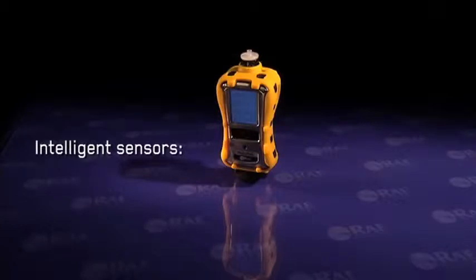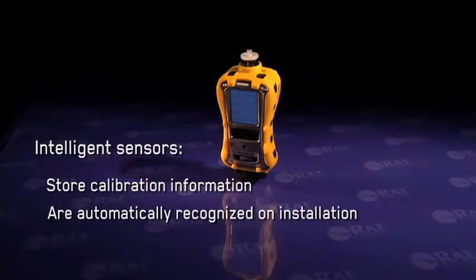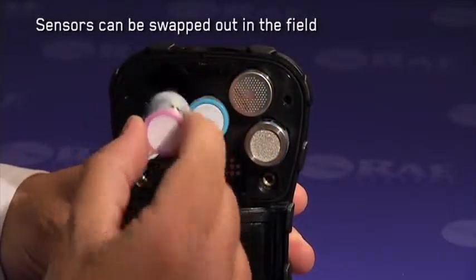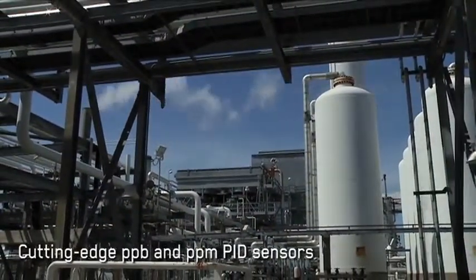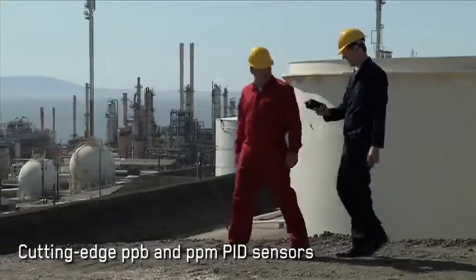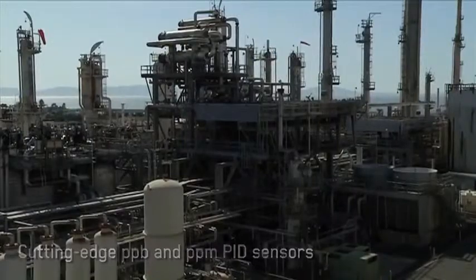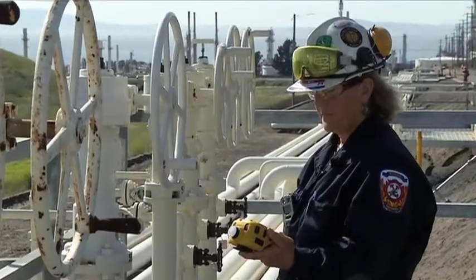The MultiRAE intelligent sensors store calibration information and are automatically recognized by the instrument upon installation, so pre-calibrated sensors can be easily swapped out in the field. RAE Systems' cutting-edge patented photo ionization sensors allow dependable linear detection in the parts per billion to parts per million range for a variety of volatile organic compounds that are virtually undetectable by any other means.